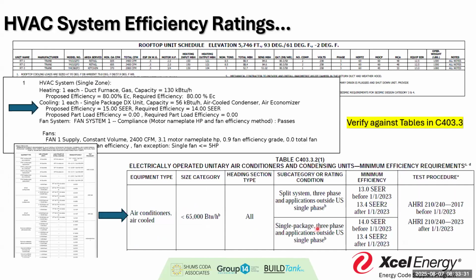Same thing with the cooling section. We're going to verify and apply. We see this again, that same system providing 56,000 BTUs in cooling, which we see it's not really, it's 52. We go over here and it's showing me an equipment efficiency rating of 13. Well, they told me it was proposed at 15.